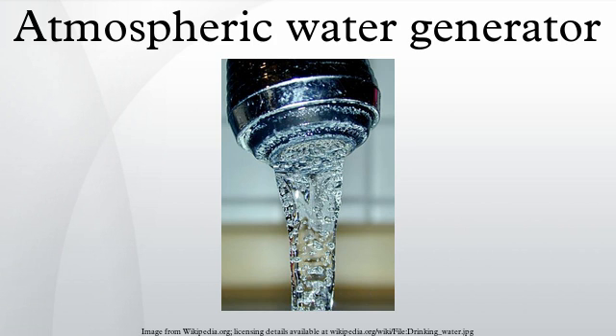Atmospheric water generators become more effective as relative humidity and air temperature increase. As a rule of thumb, cooling condensation atmospheric water generators do not work efficiently when the temperature falls below 18.3 degrees Celsius or the relative humidity drops below 30%. This means they are relatively inefficient when located inside air-conditioned offices. The cost-effectiveness of an AWG depends on the capacity of the machine, local humidity and temperature conditions, and the cost to power the unit.